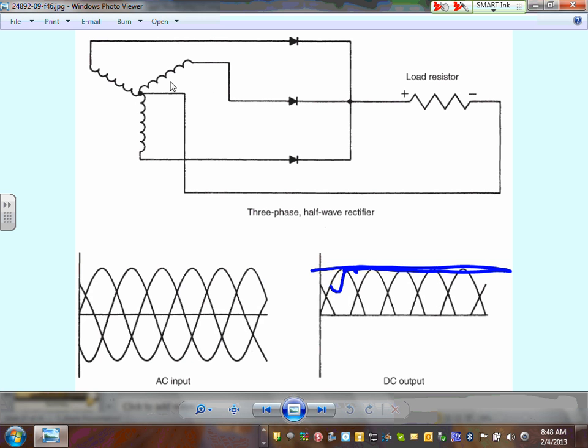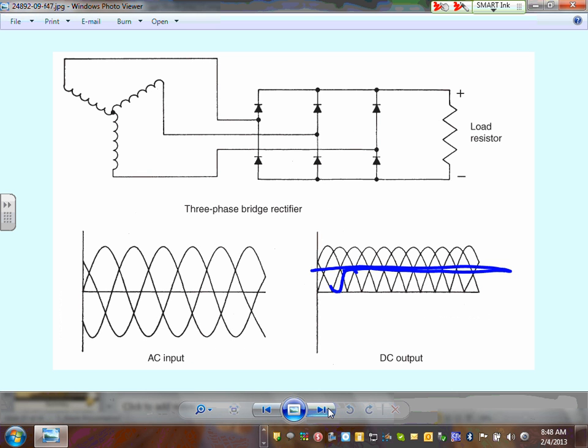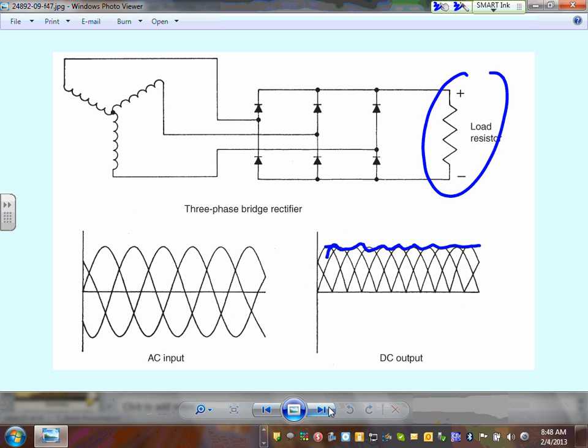That's how you get the AC 3-phase 480 into this value. Here's a much better one when you bring in a 3-phase. Look at that. Don't you guys think that this is as close to a DC as you can get? Dumping it right across this DC motor. So anyway, that's your 3-phase bridge rectifier. They call it a 3-phase bridge rectifier. That's your DC drive. That's what your DC drive does for a living.